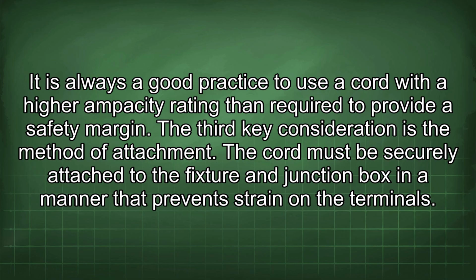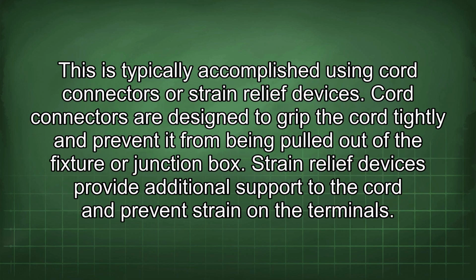It is always a good practice to use a cord with a higher ampacity rating than required to provide a safety margin. The third key consideration is the method of attachment. The cord must be securely attached to the fixture and junction box in a manner that prevents strain on the terminals. This is typically accomplished using cord connectors or strain relief devices. Cord connectors are designed to grip the cord tightly and prevent it from being pulled out of the fixture or junction box. Strain relief devices provide additional support to the cord and prevent strain on the terminals.